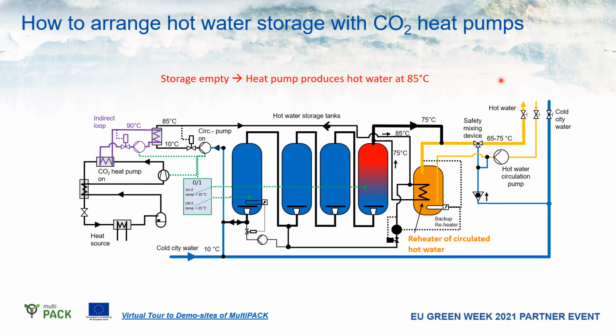So in case a lot of water is taken out in the house, then the cold water is entering the storage tanks. That's why it's very important to make this with a sufficient diffuser part. In this case, I show you empty tanks, meaning these tanks are unloaded and the heat pump starts. When the heat pump starts, around 10 degrees cold water is utilized. The amount of water is controlled so that the supply temperature is in this case 85 degrees.